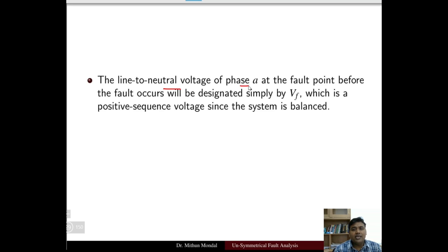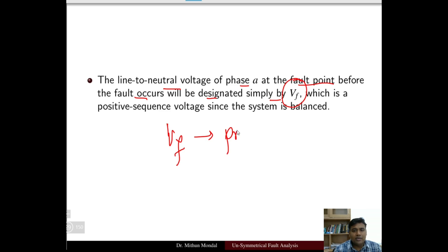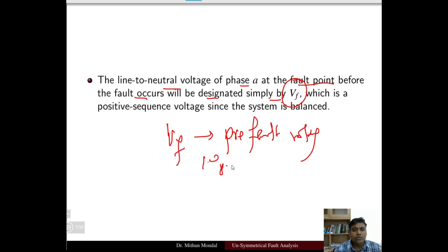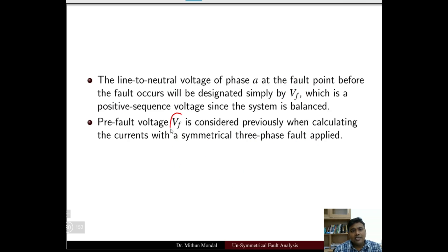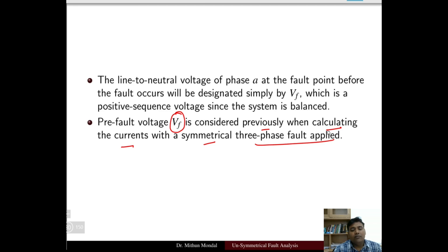The line to neutral voltage of phase A at the fault point before the fault occurs is designated as Vf, the pre-fault voltage. In per unit system, the pre-fault voltage is taken as 1 per unit, which is essentially the positive sequence voltage, because before the fault occurs, the system is balanced and only the positive sequence voltage exists.